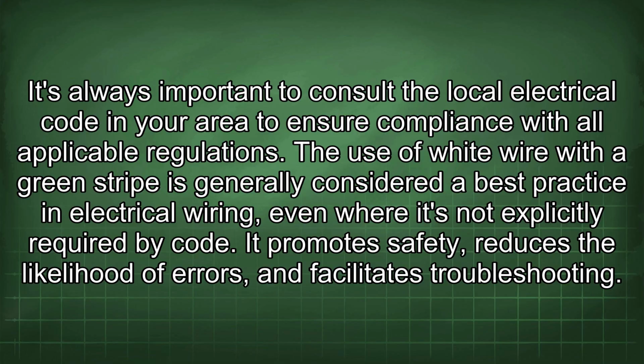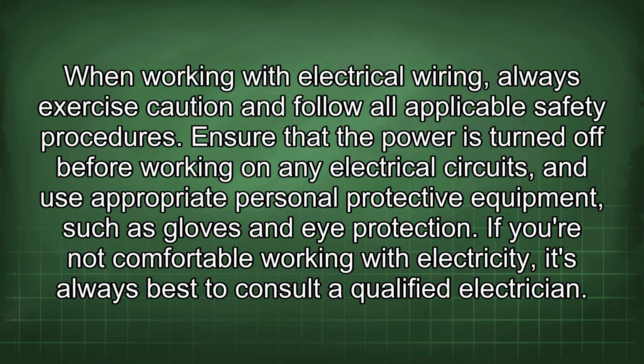The use of white wire with a green stripe is generally considered the best practice in electrical wiring, even where it's not explicitly required by code. It promotes safety, reduces the likelihood of errors, and facilitates troubleshooting. When working with electrical wiring, always exercise caution and follow all applicable safety procedures. Ensure that the power is turned off before working on any electrical circuits, and use appropriate personal protective equipment such as gloves and eye protection.